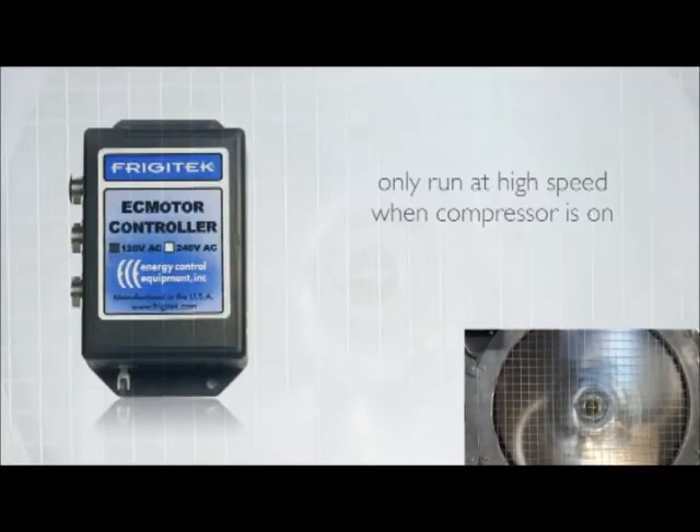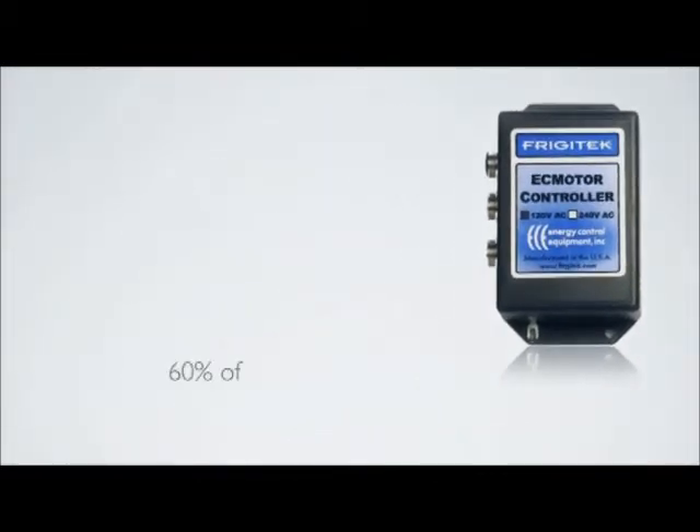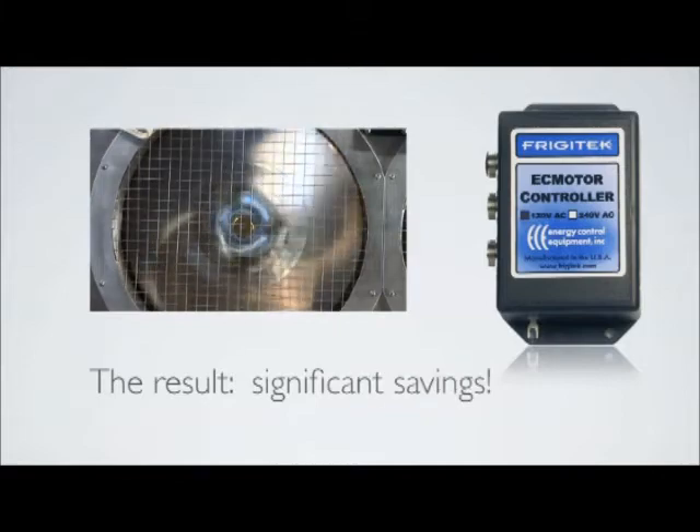With a Frigitek controller, the fan motors will only run at high speed when the system compressor is operating, which for most units is about 40% of the time. This means that for the other 60% of the time, the fan motor RPM can be lowered dramatically while still providing the necessary airflow in the box. The result? Significant savings.